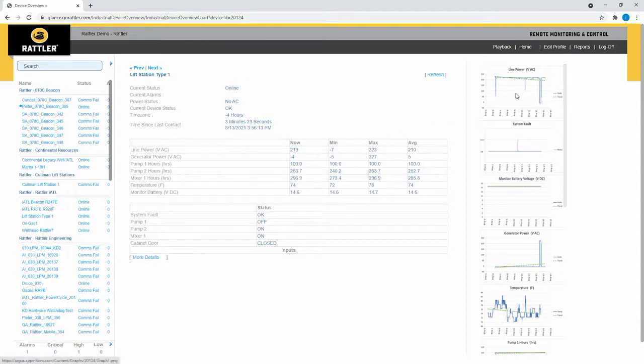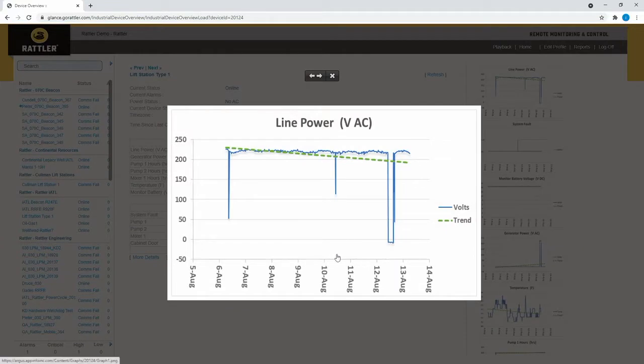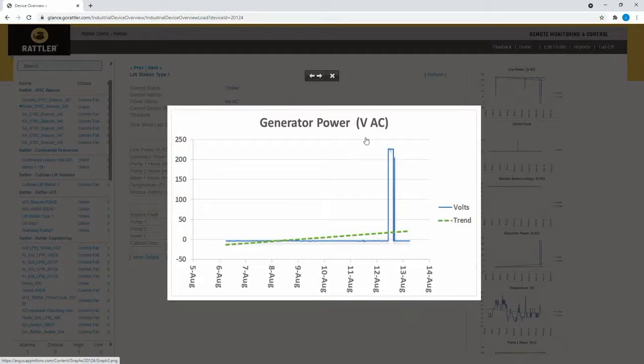These graphs illustrate some recent history over the last week. And this is, interestingly enough, a power failure yesterday of a couple of hours. You can see that the line power went out, and what happened is that the generator kicked in. This is typical of how you visualize data to tell you a story of what happened at the lift station. In this situation, they've got standby generators. In other situations they don't, and then you're just in trouble when the power fails.